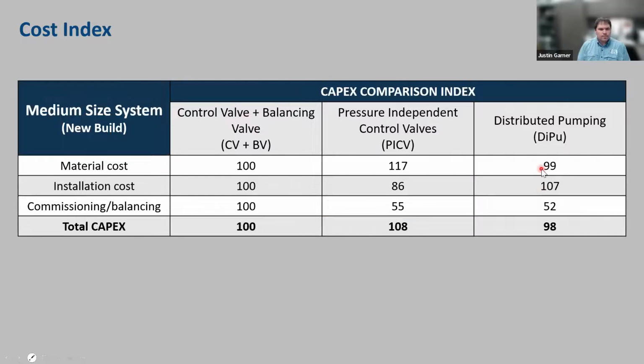As we compare a distributed pumping application, the actual smart pumps themselves cost about as much as the control valve and balancing valve combo. Installation cost goes up a little bit. We've got to bring a different electric service as opposed to what the valve will require, and then we've got that check valve to install on the return side. Commissioning and balancing would be the lowest. We feel it's the easiest of the 3 options, bringing our index down equivalent to what we see most today, which is a traditional control valve and balancing valve, and a little bit less expensive than what we'd see on a total cost for pressure independent control valves.